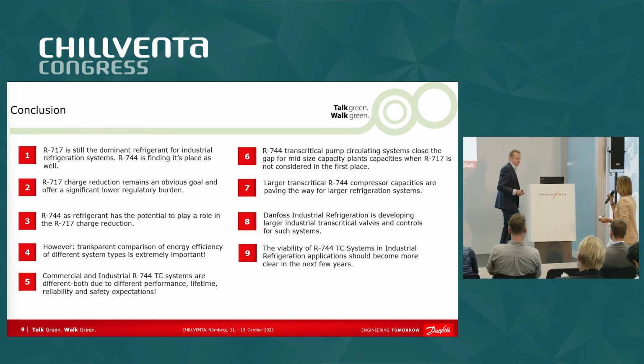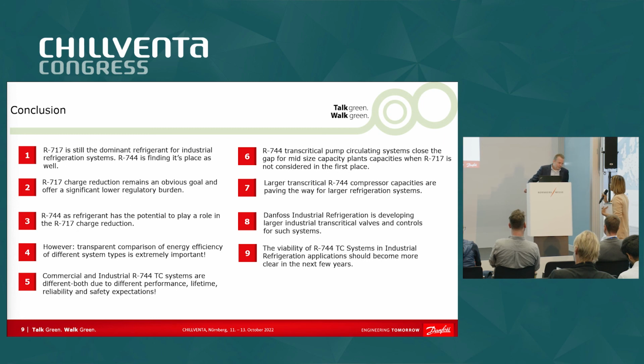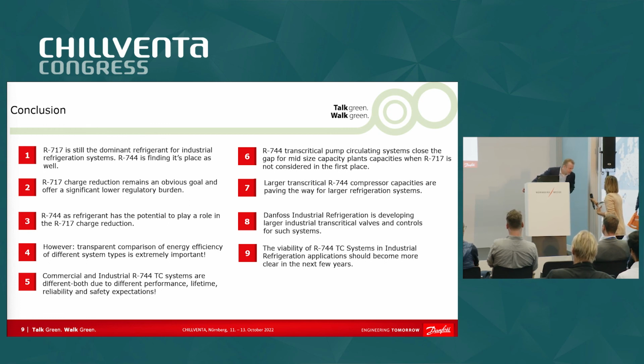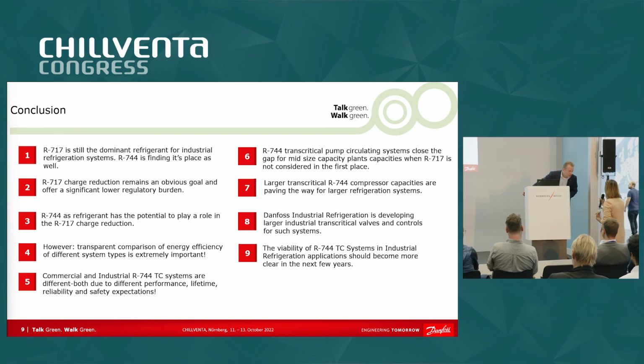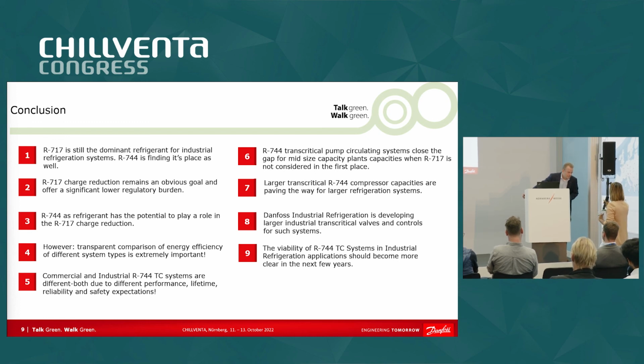Hello, Bridget Rakeshaw from Lubrizol. I just had a question. What are the lubricant considerations that you have to have in the ammonia CO2 cascade systems? Those can be considered very different refrigerants as it relates to the lubricant compatibility. So is there any special consideration that you would have to take into account in that combination system when compared to the individual ones?